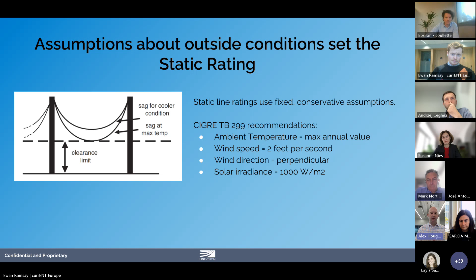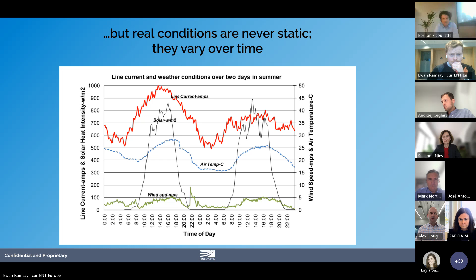So the assumptions that go into it that have to be conservative, this is just a quick image of how variable these different components are. So air temperature varies widely. Obviously, solar irradiance varies every 24 hours. Wind is variable as well. So there are all these different things that are happening in real time out there on the grid. But if you're only assuming the worst case, you're having a very set static limit for how much power you can move. Next slide.